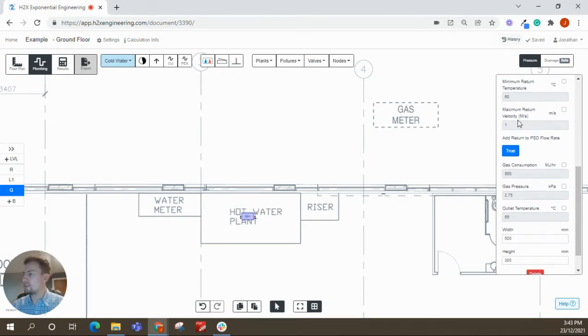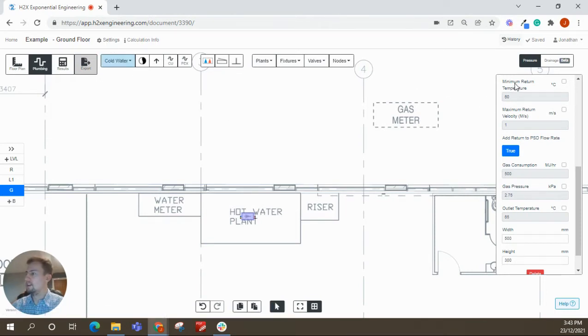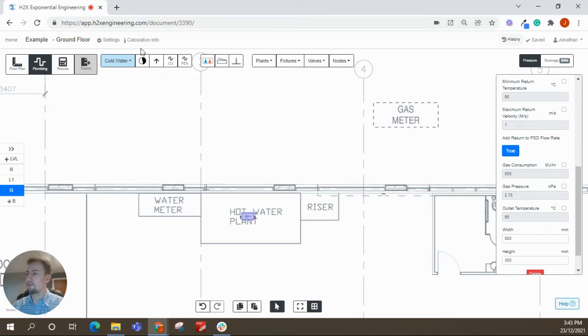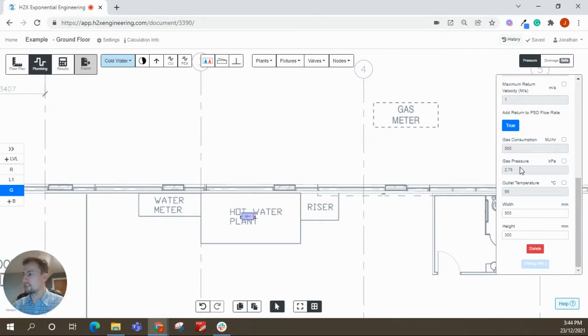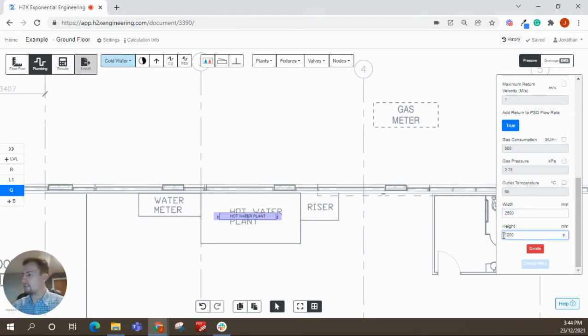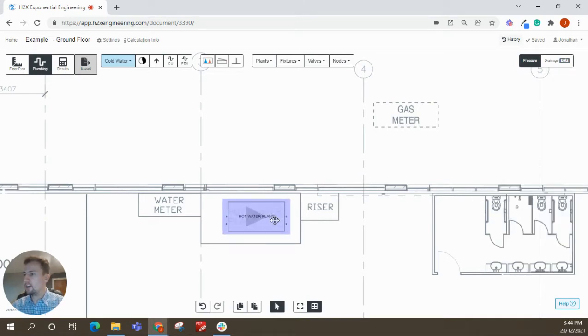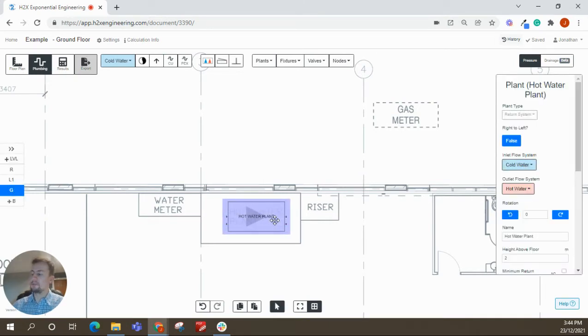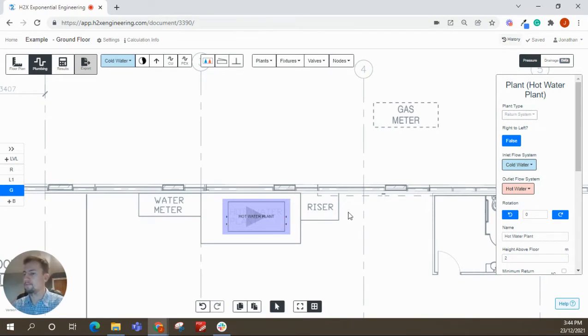For the return system part of it, so we've set the outlet temperature 65 in the flow system settings earlier. So it automatically applies a delta T of five. The velocity comes from the settings as well. So you can override these if you want to, but I'll leave them the same. You can connect gas to it, which I won't do in this video, but this is where you can change the gas consumption. And then lastly, you change the width and height here as well, just so it looks a bit more realistic. We do also have Rheem hot water plant built in. So if you go with that option, it will give you all the size and gas requirements and results for it as well.